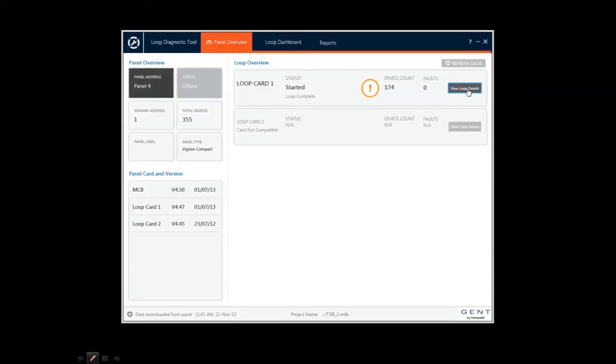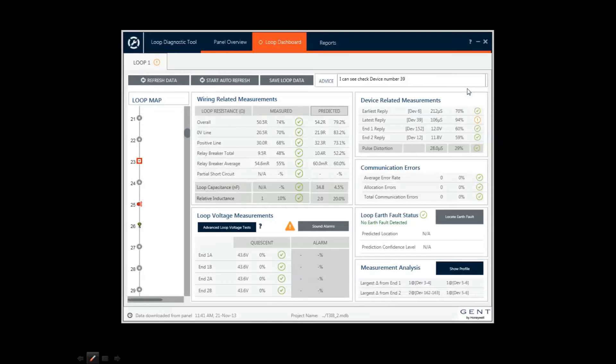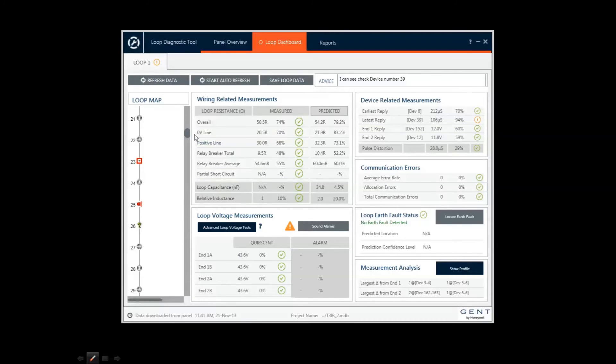I can click on the button here and see a detailed diagnostic summary for that loop. In this view, I can see the loop map and a list of results for loop wiring and device status.